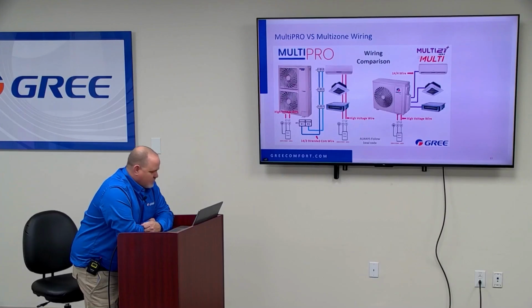That is really more geared to when you've got an existing multi-zone system that you're going to be replacing with a MultiPRO system, and getting power to the individual indoor units is going to be a little trickier than if you just use that power adapter for the outdoor unit. All it is, if you look at that power adapter, is inline 15 amp fuses in that wiring harness, so it fuses the indoor units.